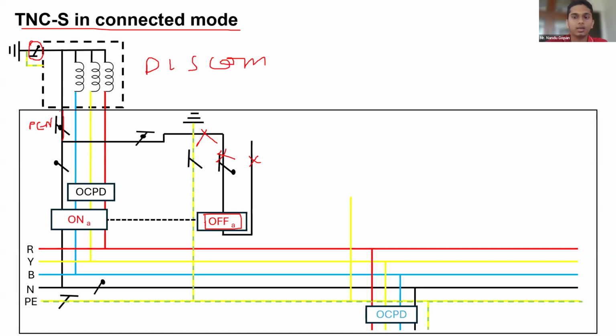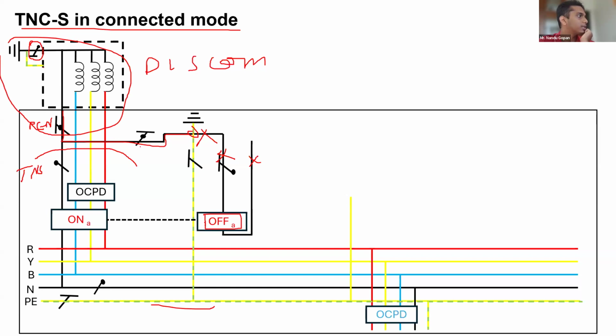The neutral and the earth is connected here, coming in this single line, and this single line is actually being connected to the PE of the installation here. So this is also a system referencing conductor. This is where the TNCS from here, this is a TNCS, the TNCS from here is being changed to TNS. So this is TNS. So the system referencing has been done here. So from here, it will be a neutral conductor, and this will be a PE conductor for the installations.